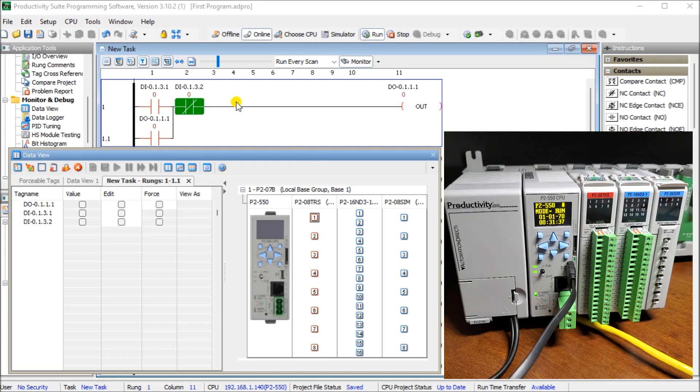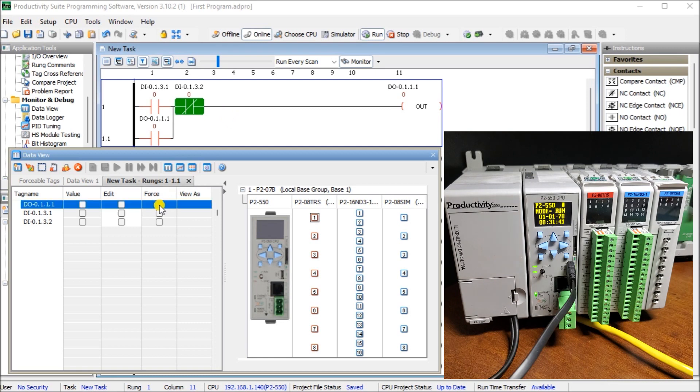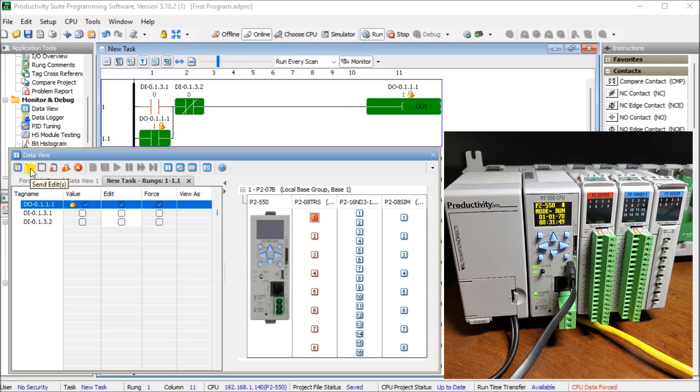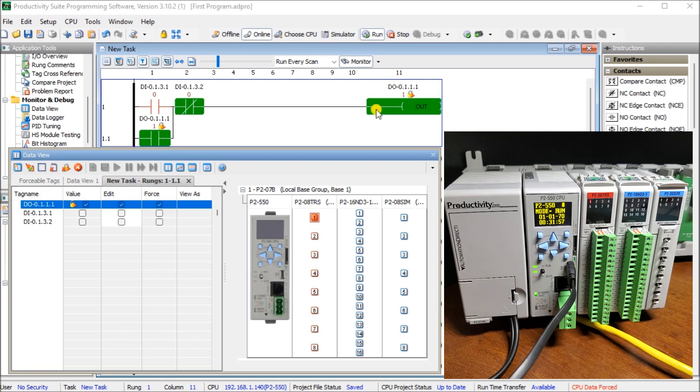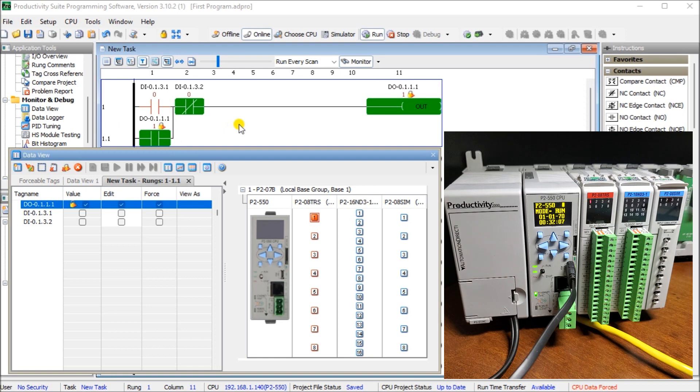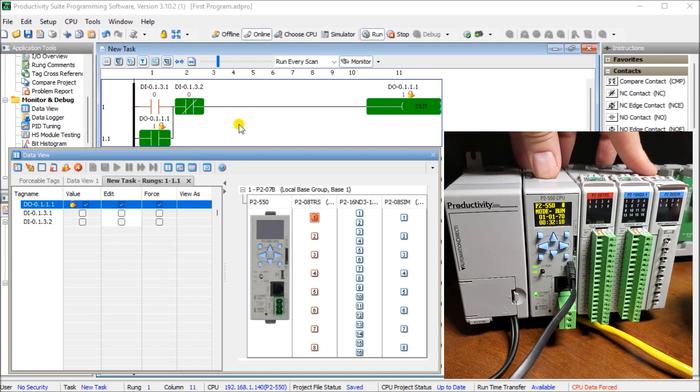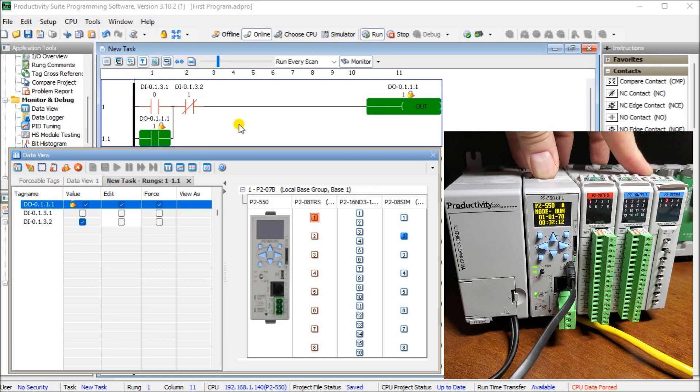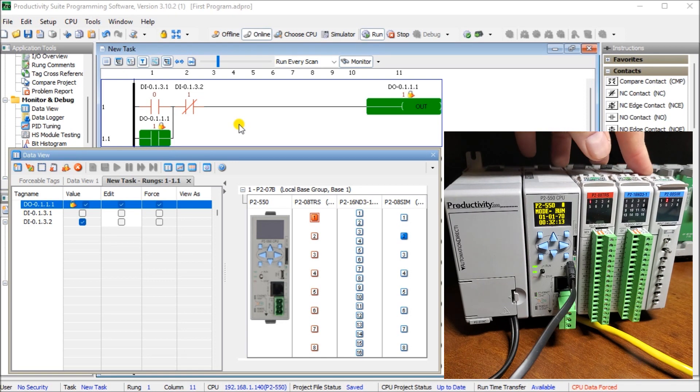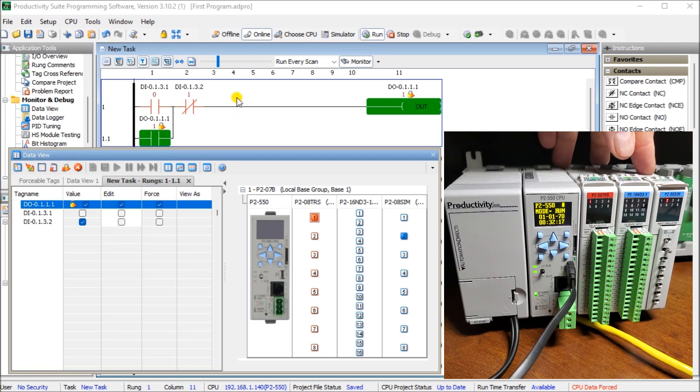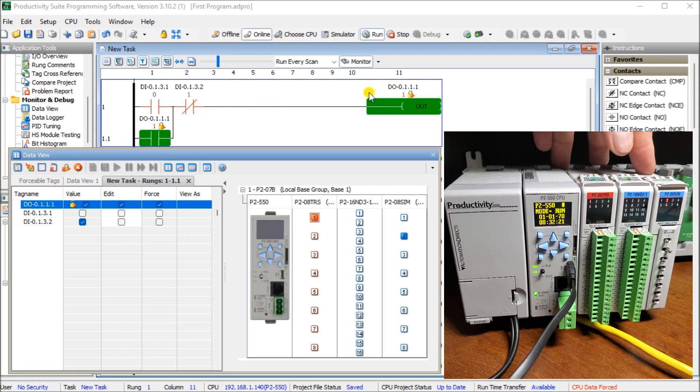Now remember also. When we have to look at the tag database. We're allowed to force. That output. If we force the output. And we will turn it on. Then we can write that. And you can see that. It creates a symbol here. That we force that output to be on. And then when that outputs on. You'll see on my ladder logic diagram. I have a symbol here. That says that it's been forced on. And that's my sealing. It's the same contact. So it's forced on. If I try to reset it. Or stop it. You will see that it does not. Stop. And there's no connection between the two. So that my scan time does not affect it.